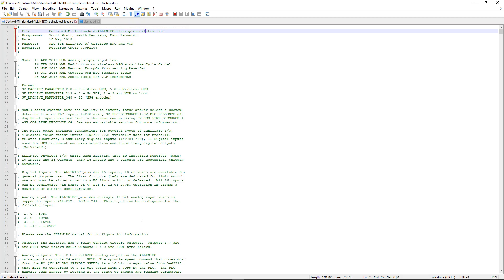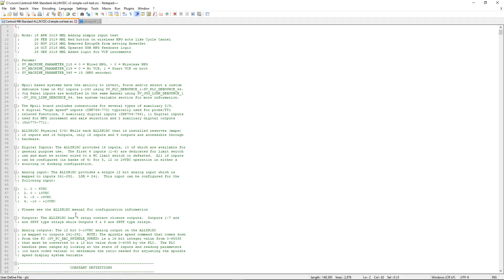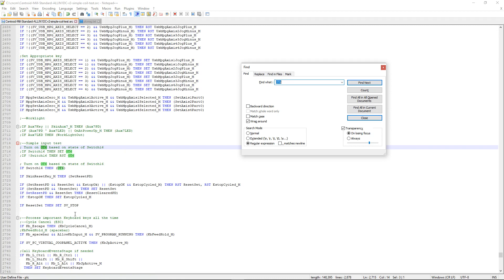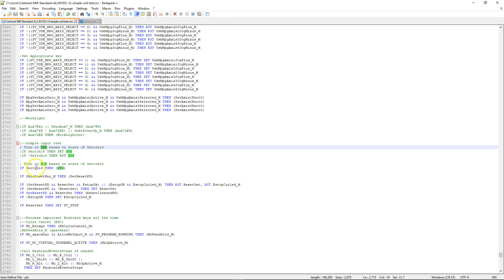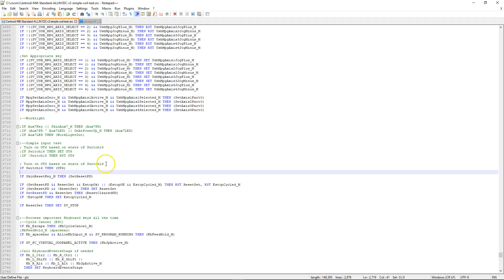Now we're going to do another simple but slightly more complicated example. We're going to turn on an output based on pressing an AUX button. Previously we defined output 6 as OT6, and I'm going to continue using OT6. I'll search in the PLC program for OT6 and find the logic for it. Rather than turning on OT6 based on a switch, I'm going to have it turn on based on the state of AUX3.